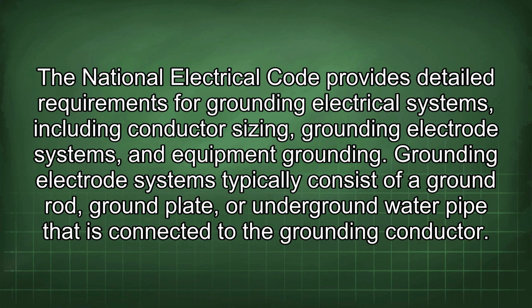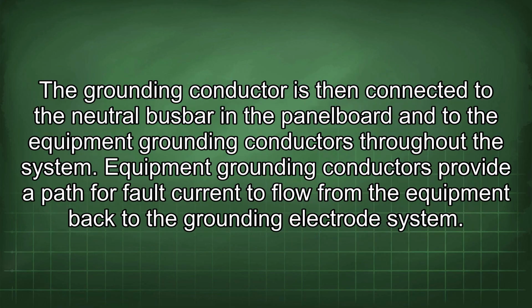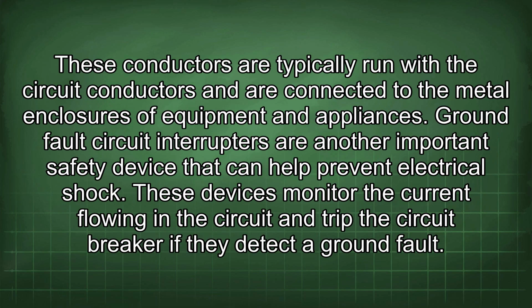Grounding electrode systems typically consist of a ground rod, ground plate, or underground water pipe that is connected to the grounding conductor. The grounding conductor is then connected to the neutral busbar in the panel board and to the equipment grounding conductors throughout the system. Equipment grounding conductors provide a path for fault current to flow from the equipment back to the grounding electrode system. These conductors are typically run with the circuit conductors and are connected to the metal enclosures of equipment and appliances.